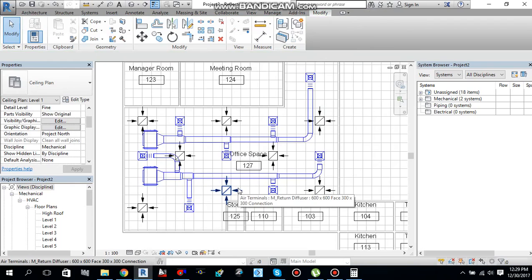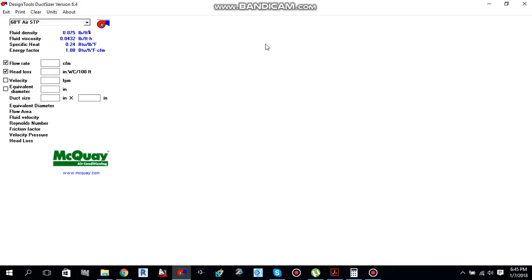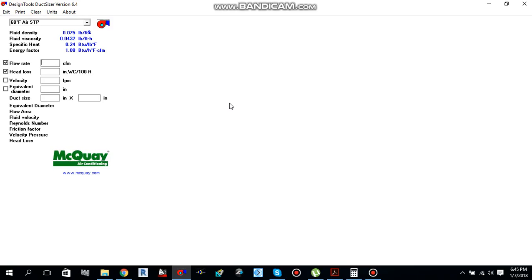This is how you do duct sizing in Revit. In this part of the video I will show you how to calculate duct size using the duct sizing program. I have opened a duct sizing program. For duct sizing you must provide inputs like flow rate and head loss in order to get your duct size. For example, from the heat load calculation I have calculated 600 CFM for a particular room and I want to calculate the duct size coming out from the machine — a ceiling ducted fan coil unit.